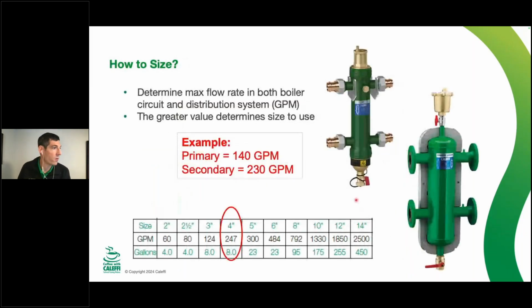So this was a pre-submitted question. How do you size these things? So let's say we know on the primary side, which we'll say is the boiler side and it has the expansion tank there, so that's our primary, we're moving 140 GPM through the boiler. We've got a different delta T design for the secondary side that's 230 GPM. We just take the bigger number, and that's what we want to accommodate with our maximum size for our chart. Whoever's making the hydro separator, that's what we're looking for there.